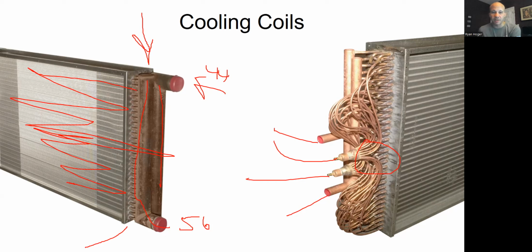So once we've identified that we have chilled water in the air handler, now we can decide if we want to make this into a heat pump system. Our decision is going to be much different than when it was a DX system. When it was a DX system, direct expansion on the right, we just decided what to do for that particular zone. If it's chilled water, chances are this air handler doesn't have its own chiller. That happens once in a while. We have a one-to-one relationship with a chiller and a large air handler, but it's not common at all.